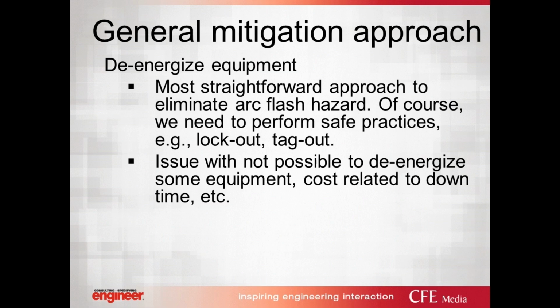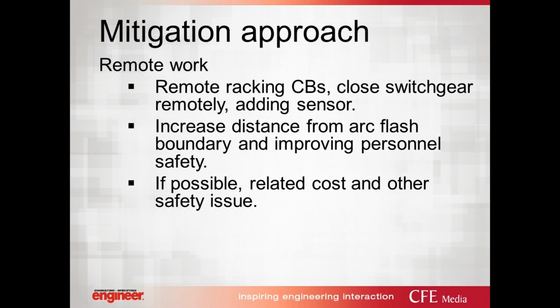The first one is de-energizing equipment, which as we all know is the most straightforward approach to eliminate the arc flash hazard. Of course, we need to make sure that we follow proper practice, such as lockout/tagout. The downside is that because you have to de-energize the equipment, there is downtime and costs related to this time. And in some cases, you really cannot de-energize some safety-related equipment that has to be operating all the time. However, that is the most straightforward mitigation approach. We always practice that if the incident energy is so high, sometimes we don't have a choice but to select this first approach.